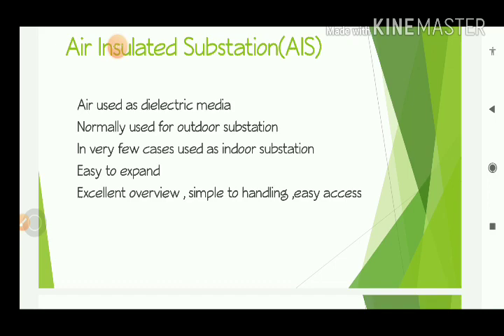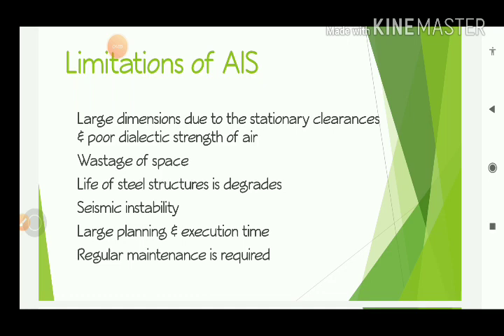The limitations of air insulated substation are: it has larger dimensions due to statutory clearances and poor dielectric strength of air; wastage of space because of large area requirements; life of steel structures is degraded due to chemical reactions as it is placed outdoors; seismic instability due to environmental aspects like flood, storm, and earthquake; large planning and execution time because components are large; high erection time; and regular maintenance is required.